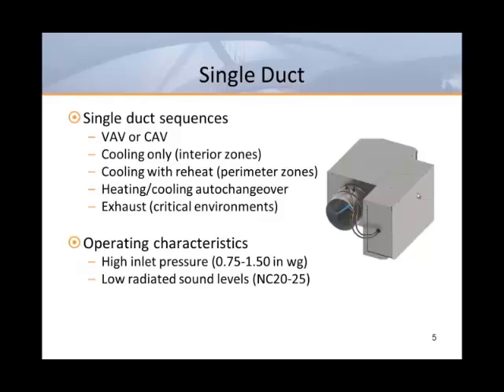If an air handler only supplies cooling, then interior zones will use cooling only units while the perimeter zones would most likely use some sort of heat. In this situation, any heat located at the box would be reheat. The box controls could also be used to operate auxiliary heat, such as a fin tube heater or a radiant panel. When there's heat in the air handler, it may be necessary to provide auto-changeover controls so that the box can reverse its operation to provide both VAV heating and VAV cooling.